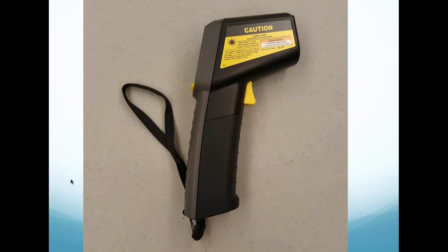I had one facility, one person tell me, Nick, I need to buy new steam traps. I said, okay, really? He said, well, yeah, I shot it with a temperature gun and it's completely cold. I said, number one, is the steam system on? Number two, do you or have you ever cleaned the strainer out in front of the trap? He said, no. I said, put a hose on it, clean it, back flush it, and then call me back and tell me what you find. He said, Nick, I don't need to buy any steam traps. The strainer was plugged. I said, okay, thank you.